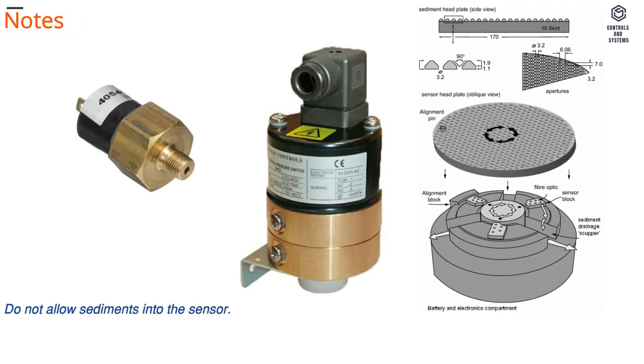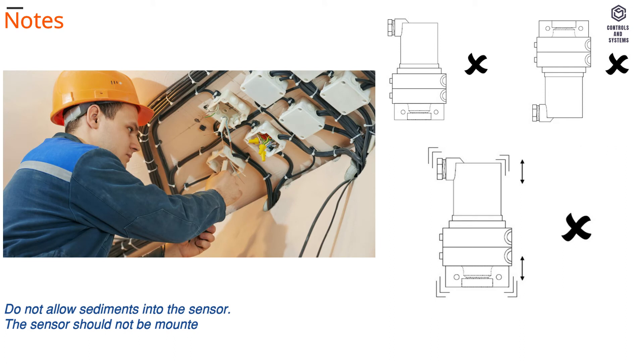Notes: do not allow sediments into the sensor. The sensor should not be mounted so that the direction of oscillation coincides with the sensor's central axis.